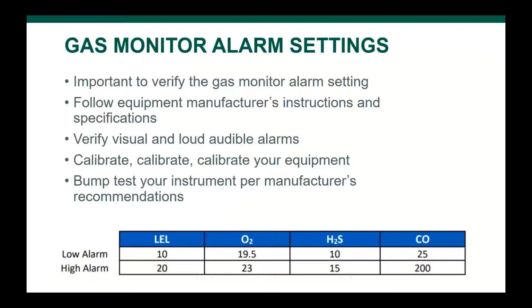So I cannot stress this enough. Calibrate, and calibrate your equipment. If your equipment is not properly calibrated, you're not going to have accurate and reliable readings. And remember, workers are entering this space. Your readings have to be accurate. There's no exception. You need to do your regular calibration, especially if the monitor has been sitting there for a while. That needs to be calibrated. I would calibrate every time you're going to use it, every day.